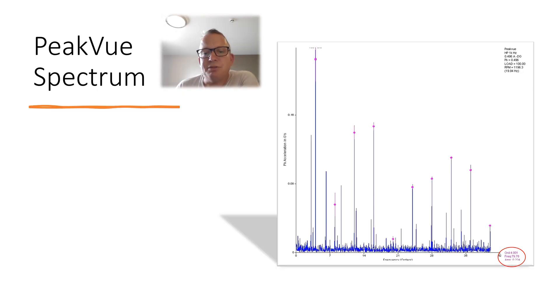So this is a spectrum we had on site, this is your PeakVue spectrum. The values are low and we can see we've got a harmonic family here. One good thing about the software is you tap the X key and find the harmonic families straight away.